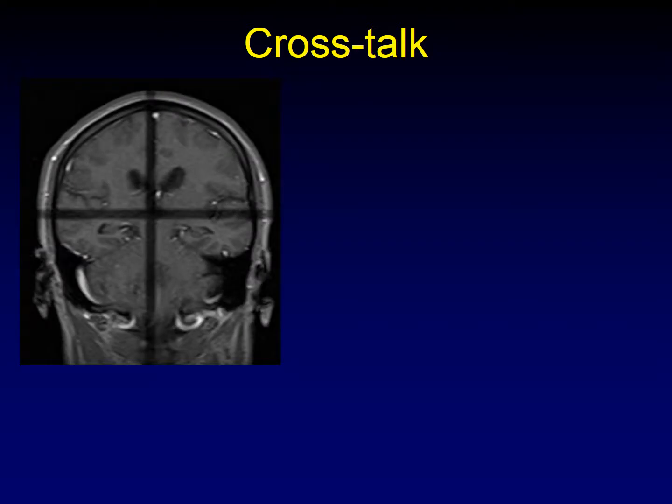To understand that interleaving artifact, we should first talk about the crosstalk artifact. Crosstalk artifact happens when two images are acquired either at the same time or one right after each other, and they are too close together or they cross one another. You can see this pretty frequently on MR images. For example, if you try to do all of your initial prescription images at the same time, the sagittal, coronal, and axial images will crosstalk with each other, creating dark bands.